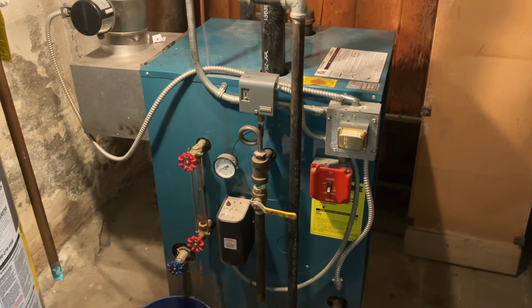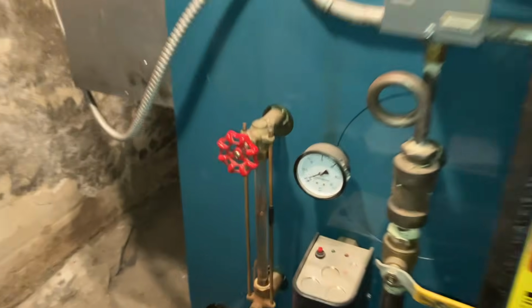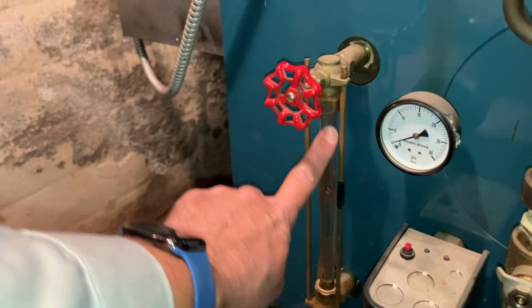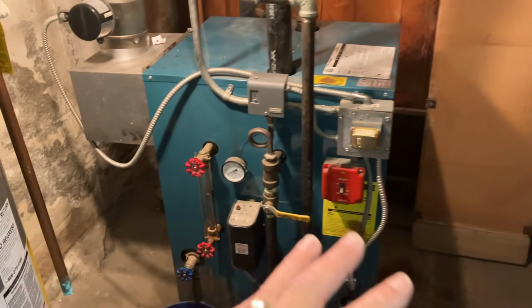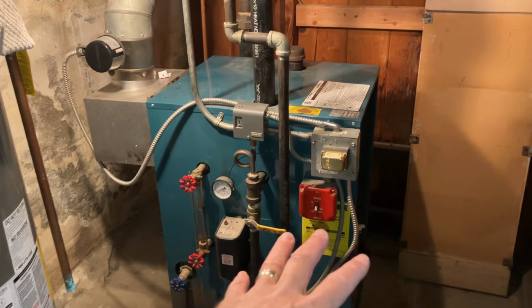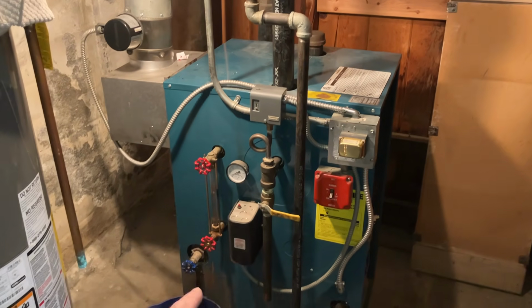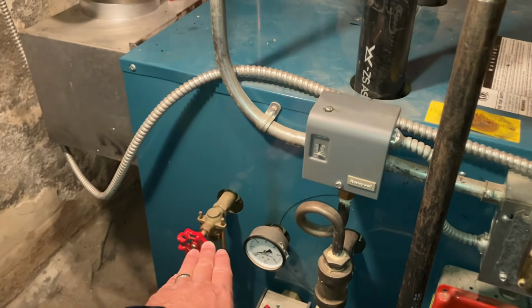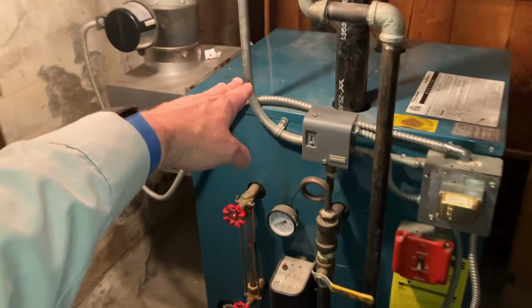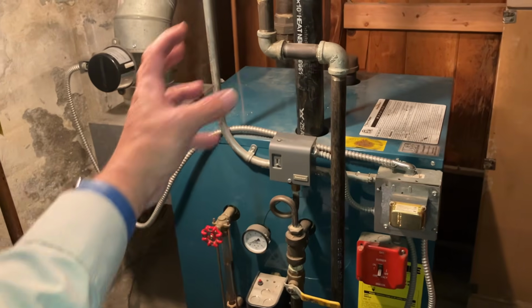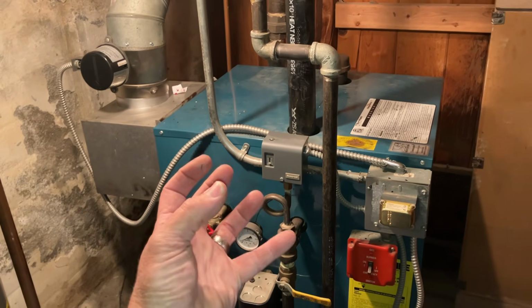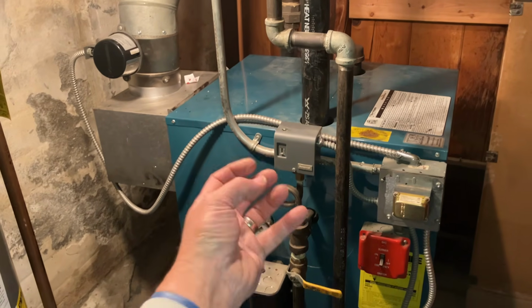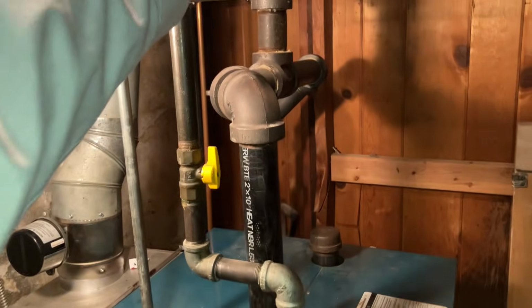But, word of advice, if you got a steam heating system, which is indicated by having a sight glass like this on the side of your boiler, before you get into taking the thing apart and cleaning it, fill up the boiler to the top of the sight glass, then count to about 15 or 20. And that's going to allow the whole entire cast iron block, or the chest, the cavity of those sections, to be completely filled with water, as well as some of the piping up here as well.